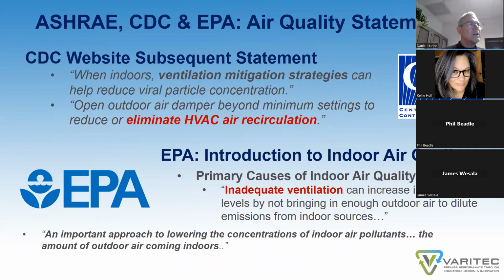Well, the CDC argues as well that when indoors, ventilation mitigation strategies can help reduce viral particle concentration. And consequently, it says open outdoor air dampers beyond minimum settings to reduce or eliminate HVAC recirculation. The EPA has this statement: the primary cause of indoor air quality problems is inadequate ventilation, and it advocates for increasing ventilation rates to reduce the concentration of contaminants in the space. So again, the EPA states an important approach to lowering the concentrations of indoor air pollutants is related to the amount of outdoor air coming indoors.